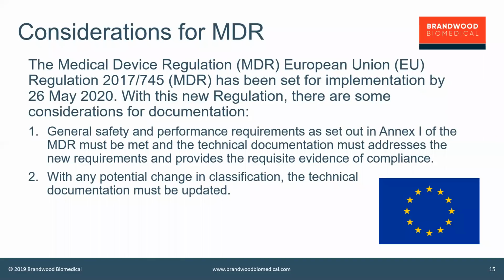That may require additional testing, unfortunately. You may have to look at your risk management file and say, we need to have more mitigation around these risks. And therefore, you may have to go back to the well and do some more verification, some lab testing, maybe even a clinical study. Now, hopefully it doesn't come to that, and hopefully you can create a CER that will address that appropriately, but even the revision of the CER needs to be considered if your device is being changed in the classification.